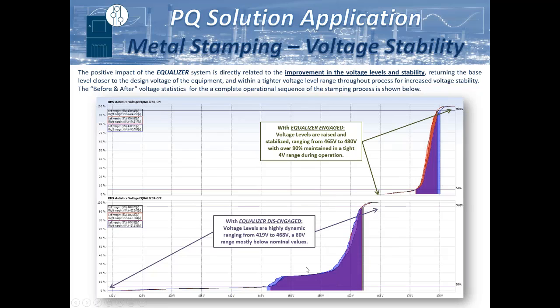This was some statistical analysis where we looked at where the voltage levels resided, both with the system engaged and disengaged. You can see this wide region with the system disengaged, in this 90th percentile zone, ranging from about 448 to about 464. But when the system was engaged, the lowest value ever reached was actually the highest value it reached prior. For the majority of the time, it resided within this 4-volt region, maintaining a very steady network.